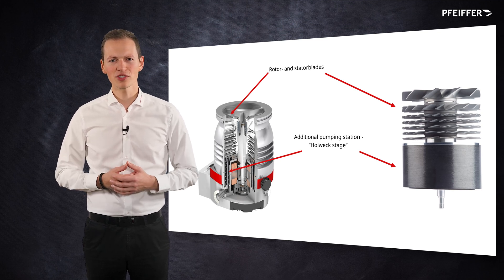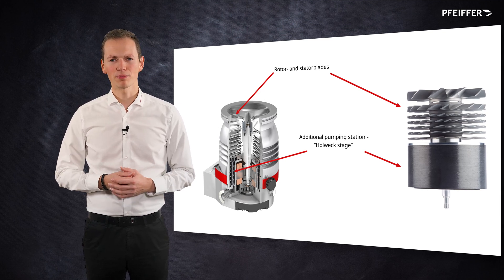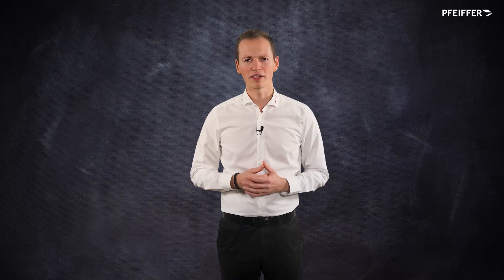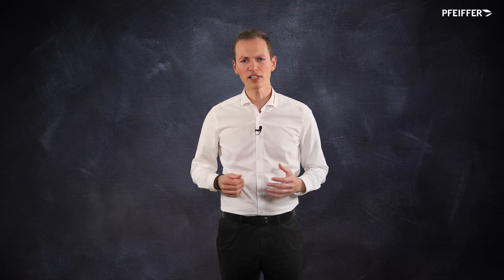The higher the compression ratio, the lower the final pressure is to be expected on the high vacuum side. In practice, however, these expected pressures can hardly be reached due to the permeation of gas molecules through seals and desorption by chamber walls.